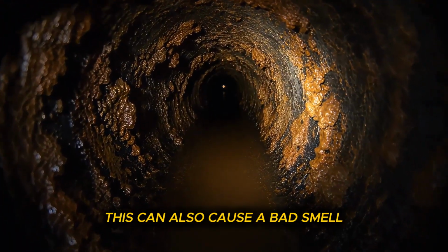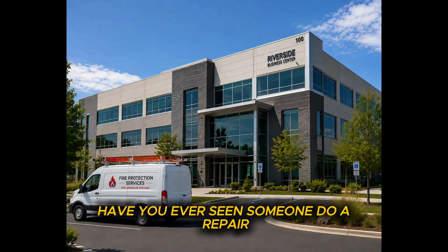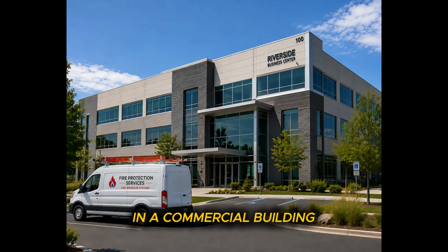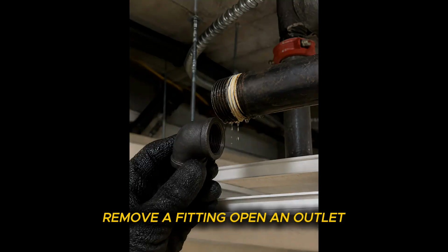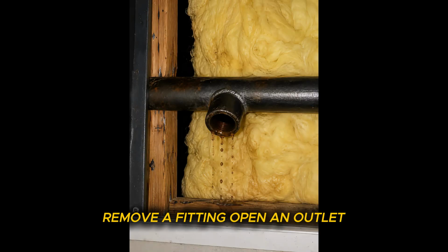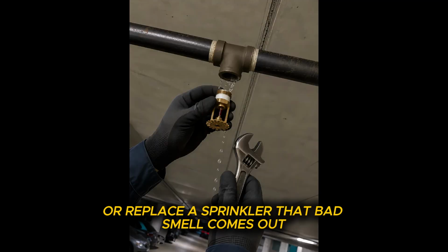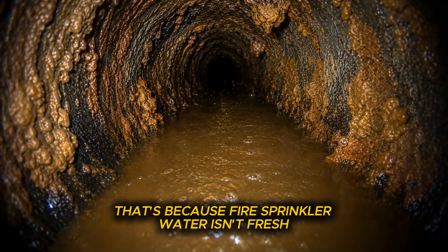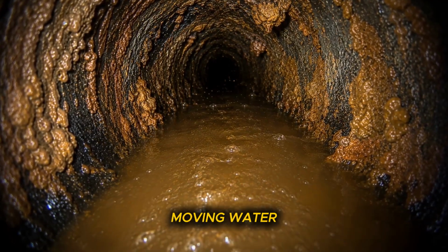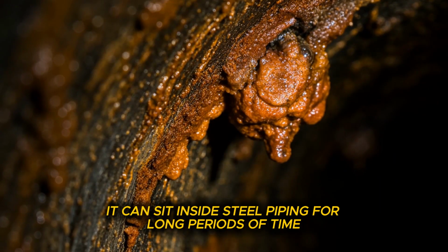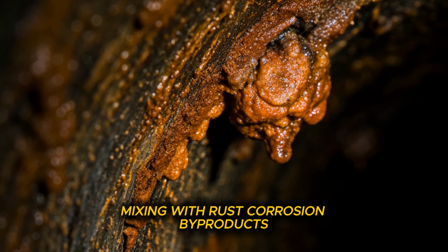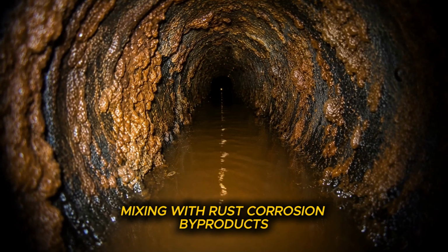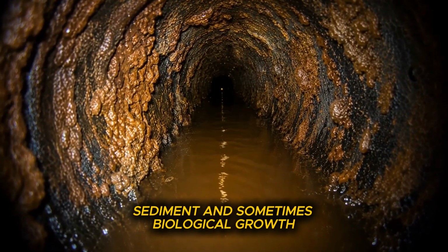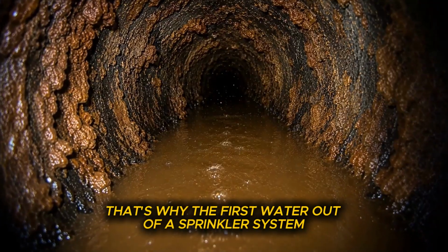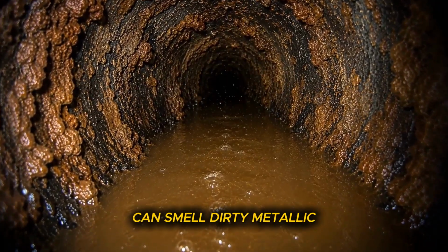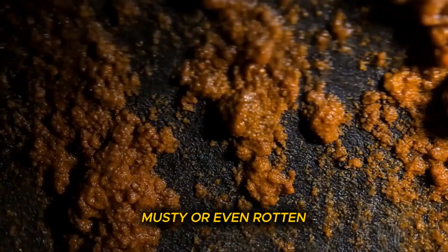This can also cause a bad smell. Have you ever seen someone do a repair in a commercial building, and once they open a piece of pipe, remove a fitting, open an outlet, or replace a sprinkler, that bad smell comes out? That's because fire sprinkler water isn't fresh moving water. It can sit inside steel piping for long periods of time, mixing with rust, corrosion byproducts, sediment, and sometimes biological growth. That's why the first water out of a sprinkler system can smell dirty, metallic, musty, or even rotten.